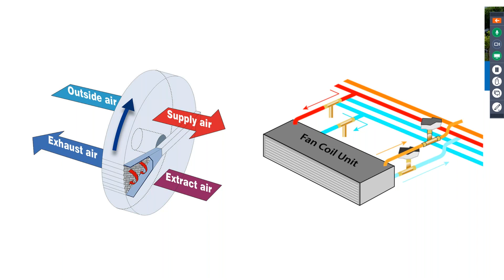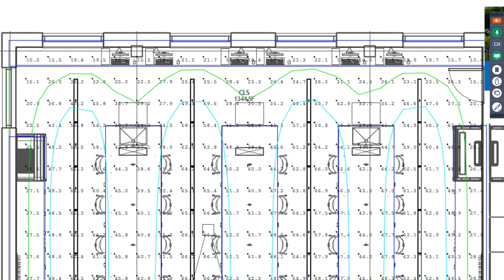Now that we've addressed the 500-pound gorilla of the exhaust and makeup air, we also needed to address the other end uses in the building. And so one of the drivers also is the lighting. And we were able to achieve a lighting power density of 0.5 watts per square foot in the lab spaces, and that still was able to maintain generally over a 50-foot candle level at most of the work surfaces. And it got to about 0.6 watts per square foot overall for the building.